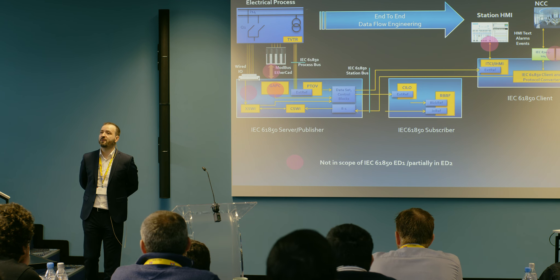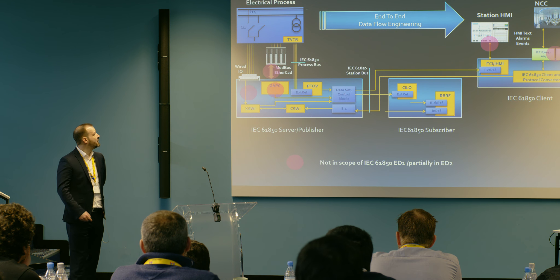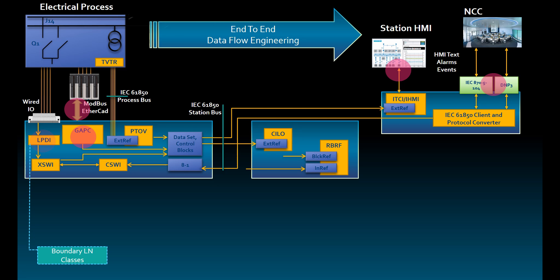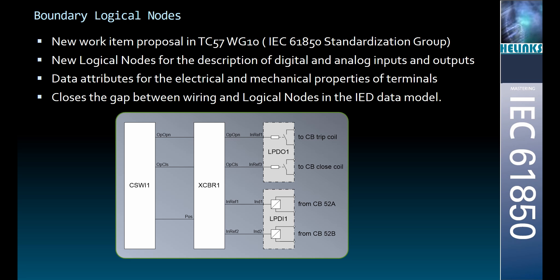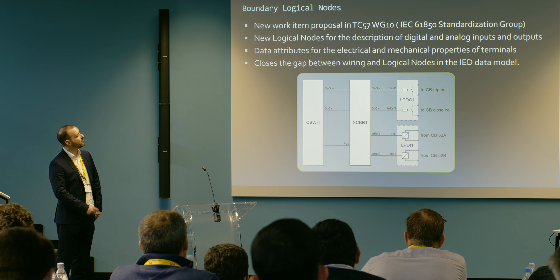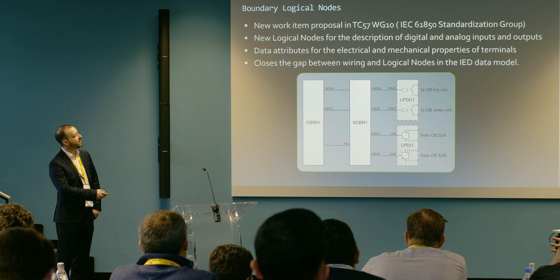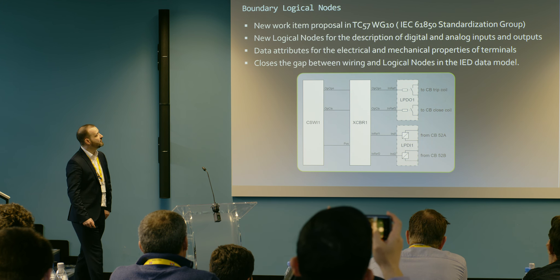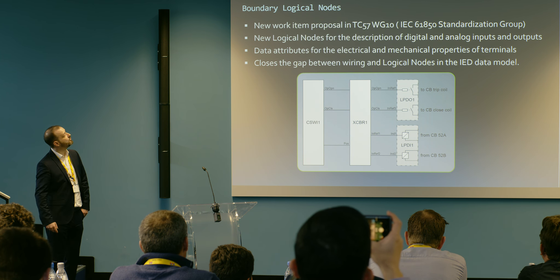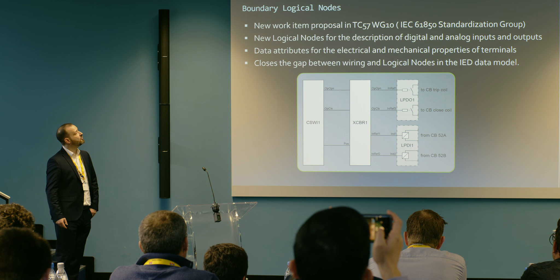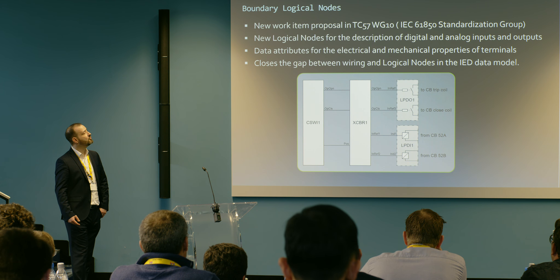To do that, you have to retrieve your vendor manual and look at that information in the relevant chapter. There is a proposal to introduce boundary logical node classes in the system node class 'L'. The LPDI node is proposed to organize exactly this information — its data attributes would be physical electrical properties, such as switchgear trip voltage or rebound parameters. In a properly designed system, you would have an intermediate between the circuit breaker controller and the actual switchgear trip coil and close coil, and with this proposed node you can model the entire chain from the electrical outlet at the primary equipment to the controlling device.